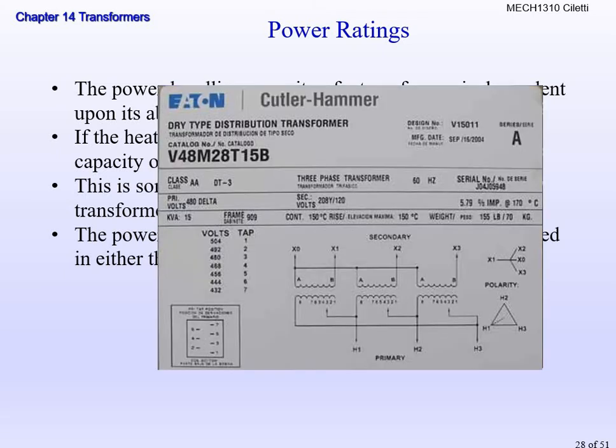If you have to buy a transformer, you can see it's on here, and we're going to look at the different taps. Think about the other info here too: there's a primary and secondary winding. Look at the bottom right corner, notice the little triangle, that's a delta connection. Just above that, with the X's, X1, X0, X2, X3, that's called a Y connection. So this is a delta to Y transformer. I know it's delta to Y and not Y to delta because I'm reading primary to secondary on the screen. We can do different types of taps on the coils to get different voltages, which we'll get into, but it's all shown on the data sheet from Cutler Hammer.